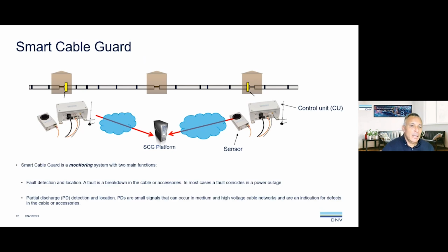Actually, we do two things. One, we can detect any type of permanent fault on the cable we are monitoring. As we're using two sensors, we measure the partial discharge inside the cable by inserting a pulse into the cable from both sides. Both sensors inject a pulse that runs through the cable that detects if there is a fault current happening on the cable. So we can precisely know that there is a fault, and also detect the location of the fault.